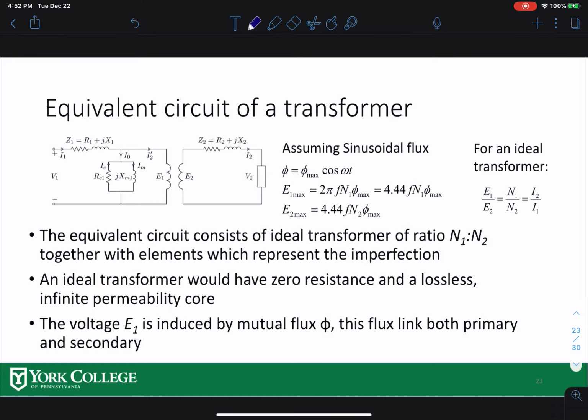When I see a transformer, inside the transformer we have a coil, right? We have coils and also a magnetic core. In the modeling, we have an ideal part of the transformer, which is this one over here. This is the ideal part of the transformer. There's no losses, nothing. But we have a winding on both sides, which is a coil, primary and secondary. The two means secondary, one means primary here. In the winding we have resistance, which is R2, and also the winding has an inductance, and we have inductive reactance here due to leakage flux. And also the magnetic core, which is a ferromagnetic material, has inductance and resistance in the core.